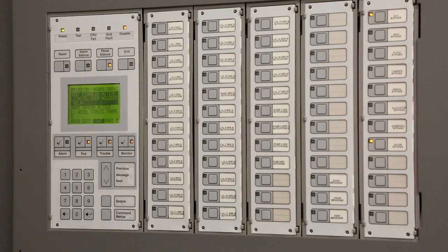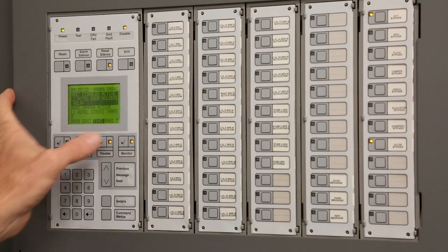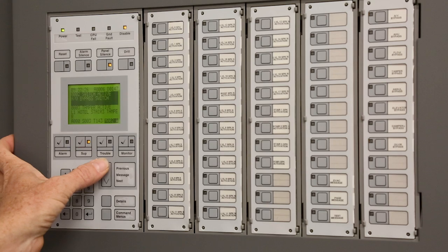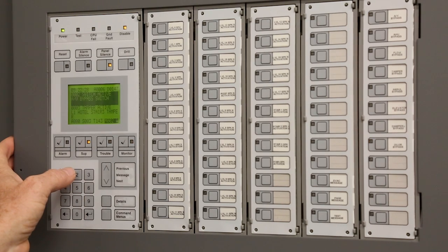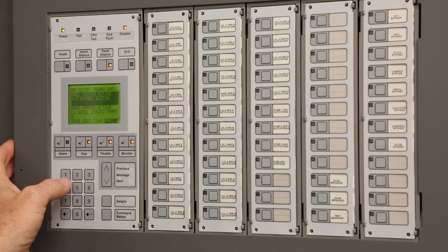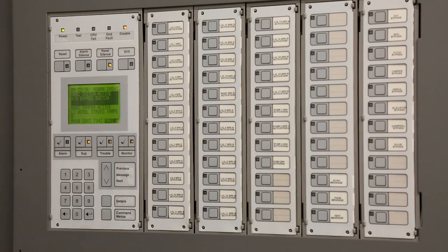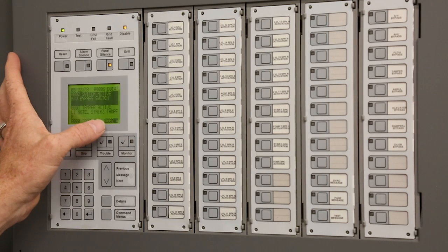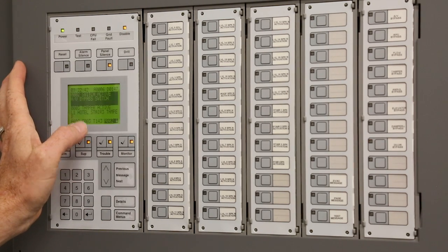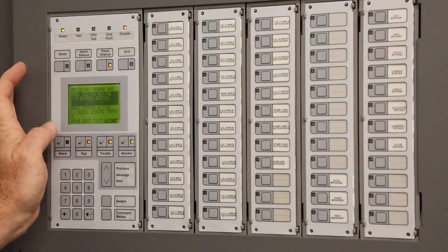Again, like I said, if I just put that other button right there, the monitor, if you notice, it went up to 2 points, and you can scroll up and down on that also, and it'll say AV bypass switch is activated, okay? So monitor points, like I said, are just switch actions, anything on the smoke control panel, any dampers. That does not report to a third party. The dialer does not report monitor points. It only reports troubles, supervisories, and alarms.